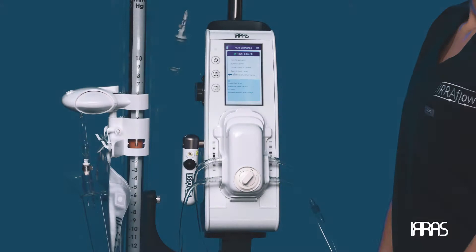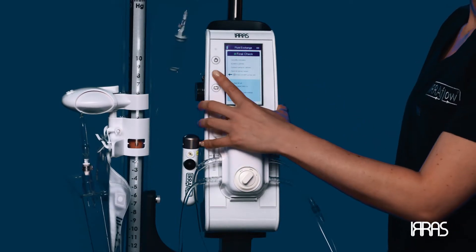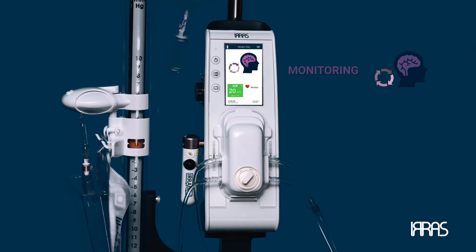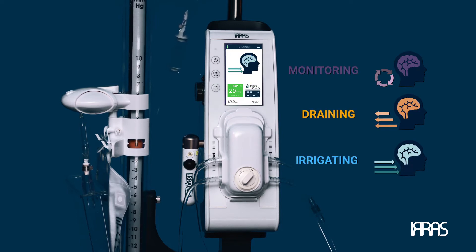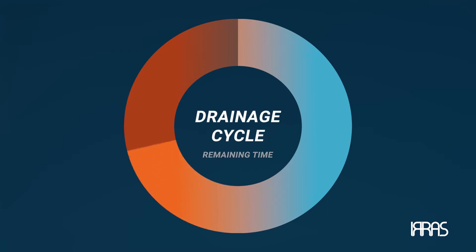Chapter 6: Treatment. Now that treatment has begun, the control unit will cycle between three phases: monitoring, draining, and irrigating. Keep in mind, the irrigation cycle will take one second, the ICP monitoring cycle will take nine seconds, and the rest of the cycle time will be applied to the drainage cycle.